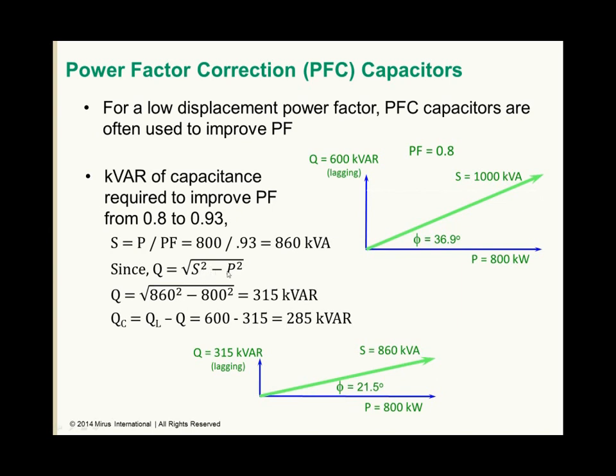apparent power squared, subtract the real power squared, and we can only have 315 kVAR of inductive reactive power to maintain a 0.93 power factor. So that would require a capacitive reactance equal to the inductive reactance prior to application of the capacitors minus our design reactive power, which means 285 kVAR. And then we will end up with the vector shown below.